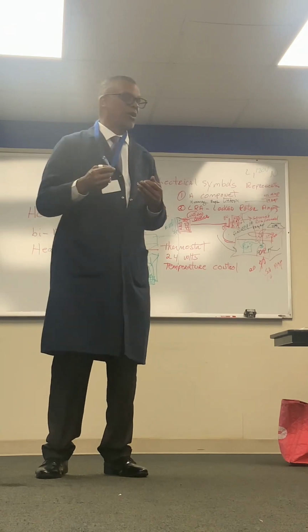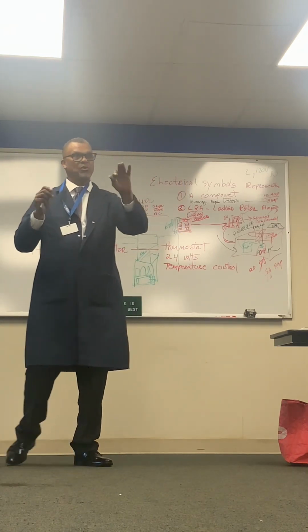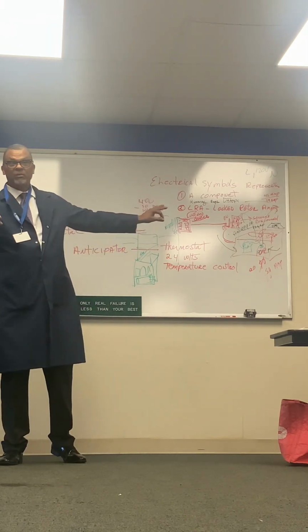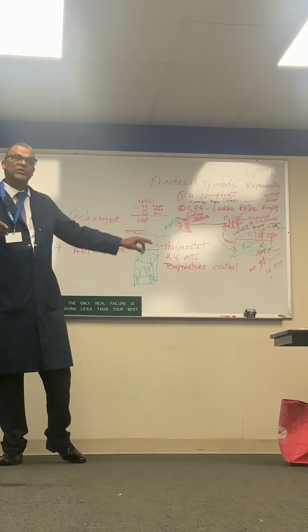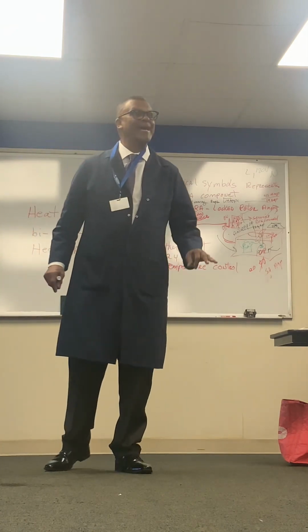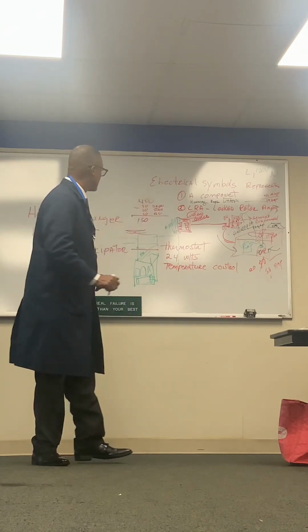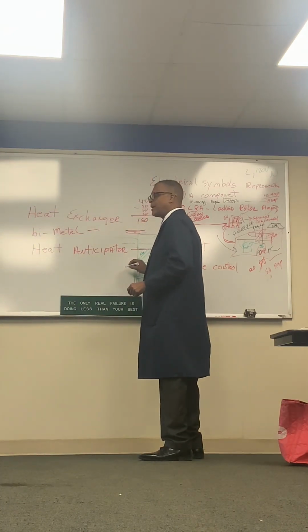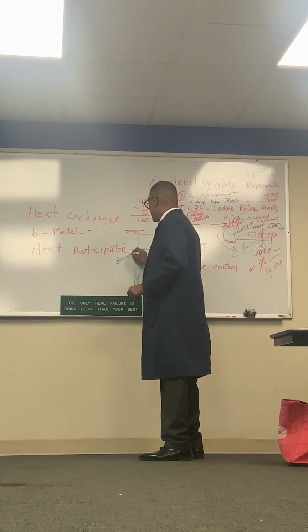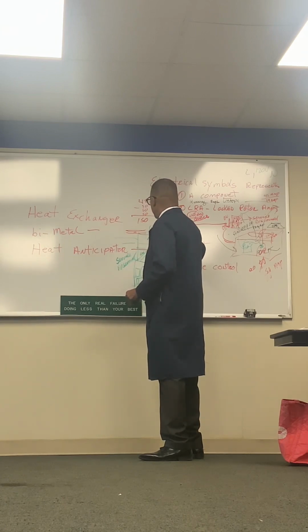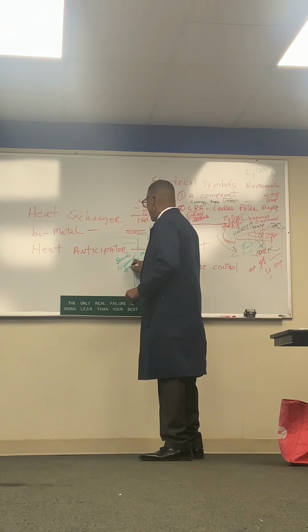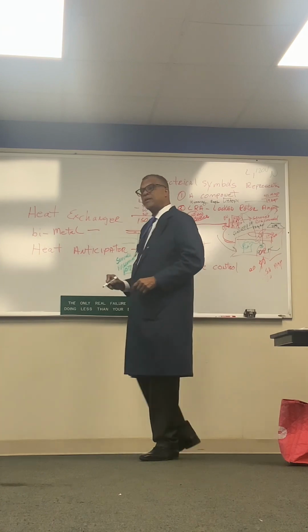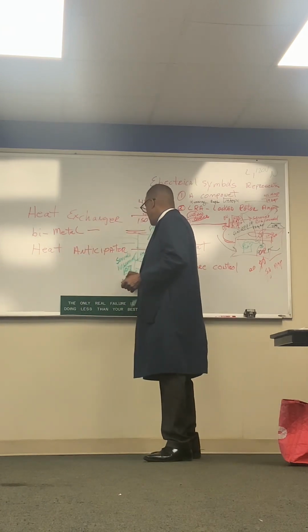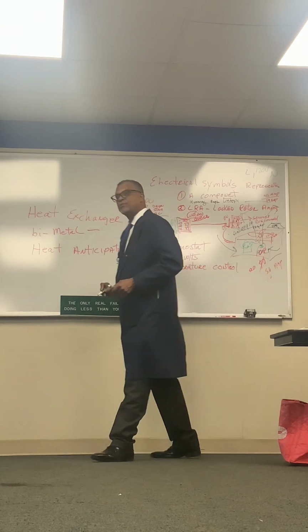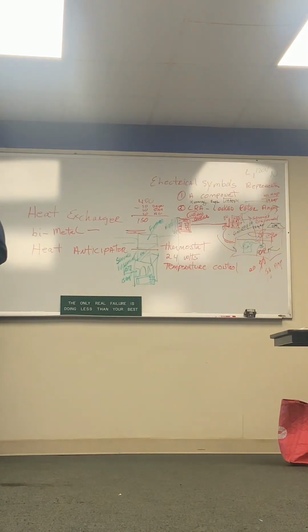Now 120 volts goes to what component compared to 220 and 240? Where does 240 go? Outside. Where does 120 go on a gas furnace? Inside. The service disconnect on a furnace comes here as 120 volts, and most of the time it only has the need for 15 amp service. That's it for a furnace, 15 amps for a gas furnace, that's it.